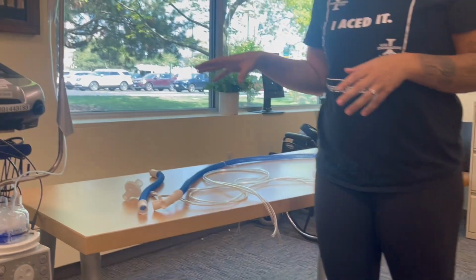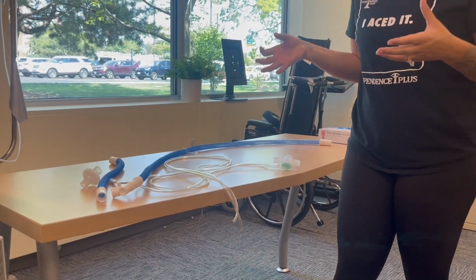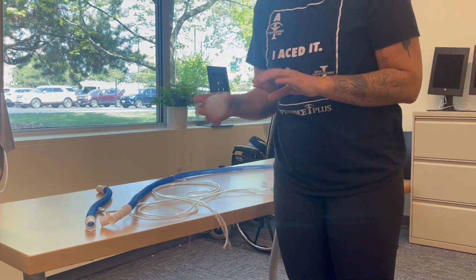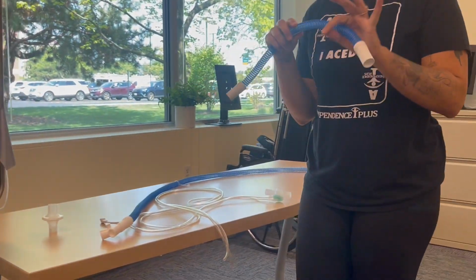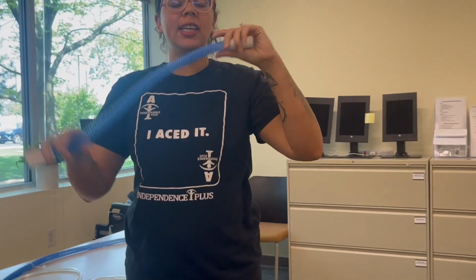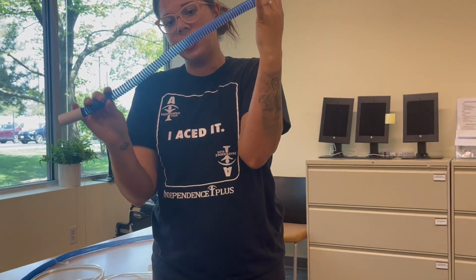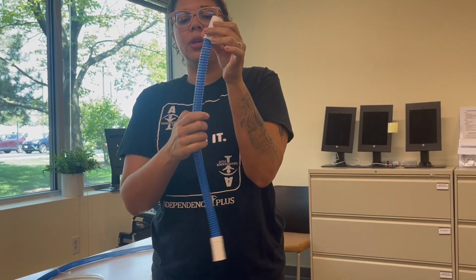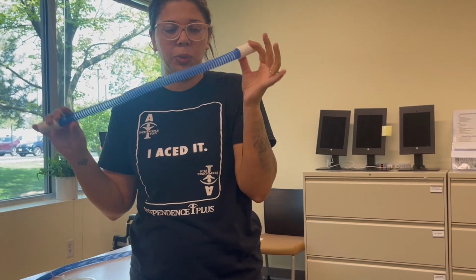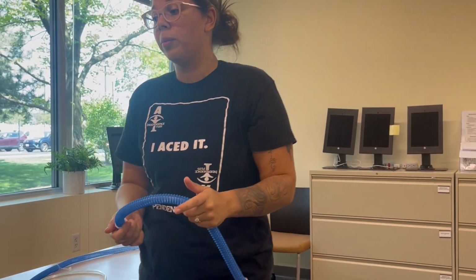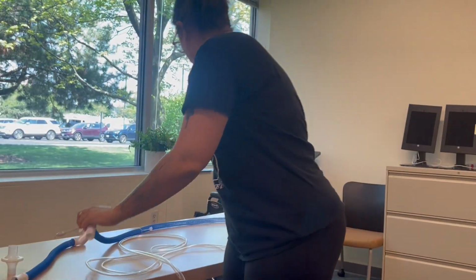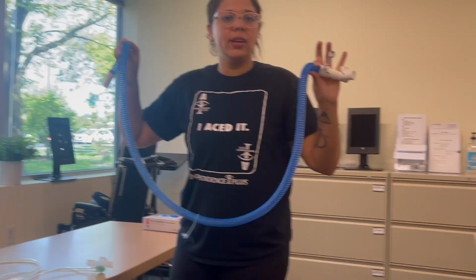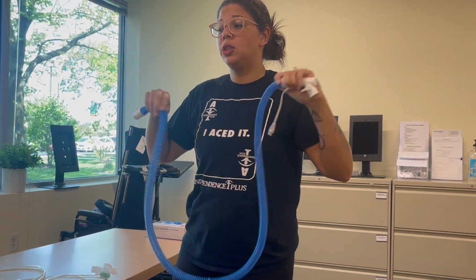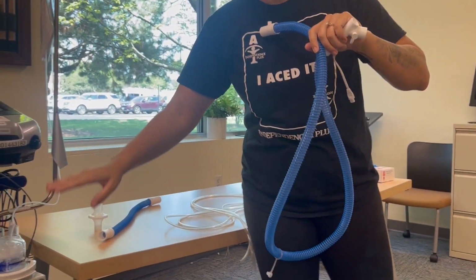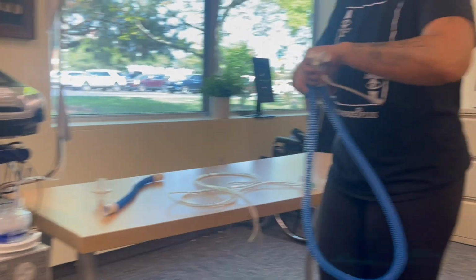So my parts to my circuit are gonna be the exact same as what my dry circuit was. I'm gonna have my bacteria filter. I'm gonna have tubing, but I need 2 pieces of tubing. So this tubing is wet tubing, that's why it's got the blue corrugation around it. Underneath this blue is the wires that heat up. So these are where heated wires are at, so it does get warm. So I have a short one, and then I'm also gonna have a long one. The long one is gonna go to the patient. The short one is gonna go from the ventilator to the MR730.